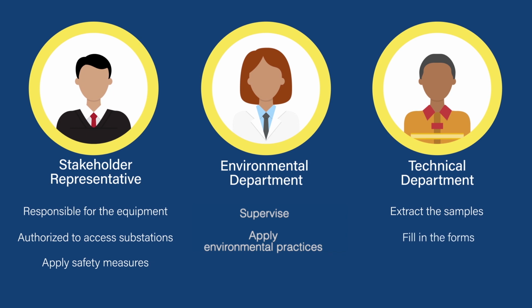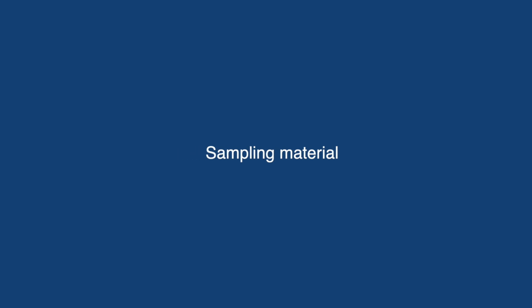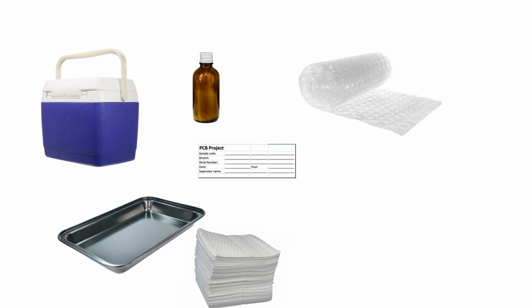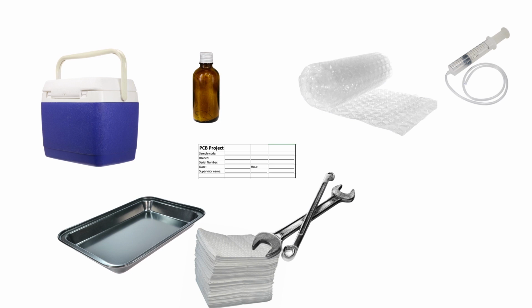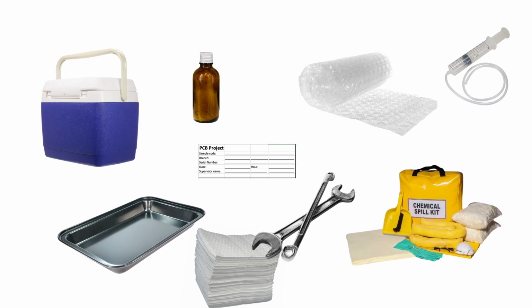Then completion of sampling forms, correct labeling of the samples, and detailed records of technical information of the transformer are essential for successful sampling. Sampling material. To collect the samples, the following materials are needed: 50 milliliter glass bottles, bubble wrap and boxes for safe transport of the samples, a tray to prevent spills, absorbent tissue to swipe oil drops, labels for samples, tools and syringes with plastic tubes in case the oil has to be sampled from the top of the transformer. In case of small and large spills, spill kits for cleaning up are needed.